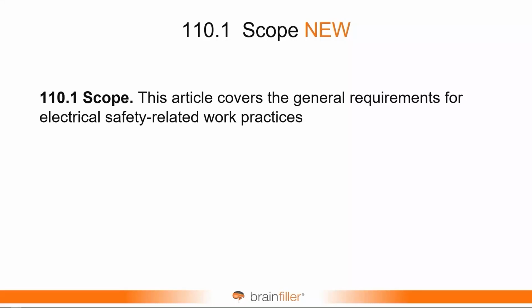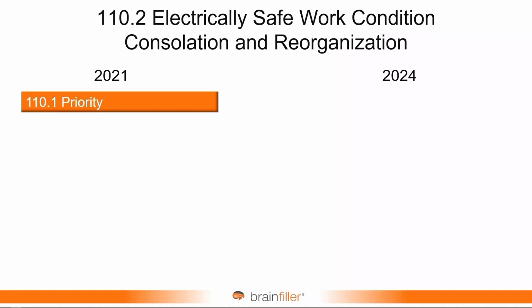The first thing to notice is there's a scope. This is one of the articles that didn't have a scope before. So there is a new scope. This article covers the general requirements for electrical safety-related work practices. The reorganization back in 2021, we had 110.1, priority. Now, you may remember that priority, it was originally introduced in Article 105, and it is the most important part of electrical safety. The priority is establish an electrically safe work condition. That's number one. And then it was moved to 110.1, the very first section in 110, because of its importance.